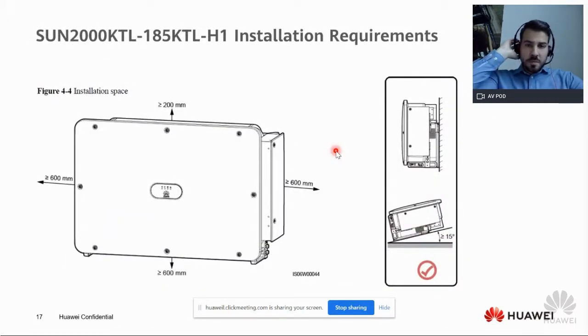So about installation, it can be installed vertically or it can be installed horizontally if you keep this 15-degree tilt. This is the maximum that the inverter can accept and can work accordingly. So this should be maintained all the way. And the reason that we can do this is that we have the fan in the inverter, so it can do horizontal operation also.